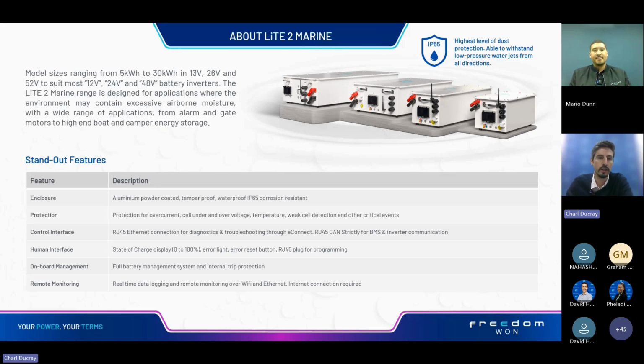On the control interface, we've got an RJ45 Ethernet connection for diagnostics and troubleshooting through the eConnect, which can now be done remotely as these units are equipped with a remote monitoring gateway. In terms of the human interface side, you're able to check the model's state of charge via the SoC display. There's an error light, an error reset button, and an RJ45 plug for programming.